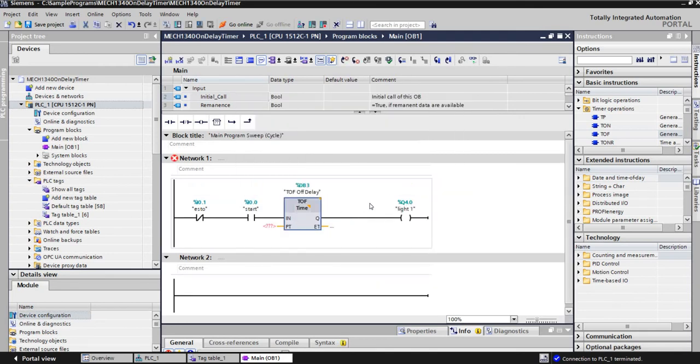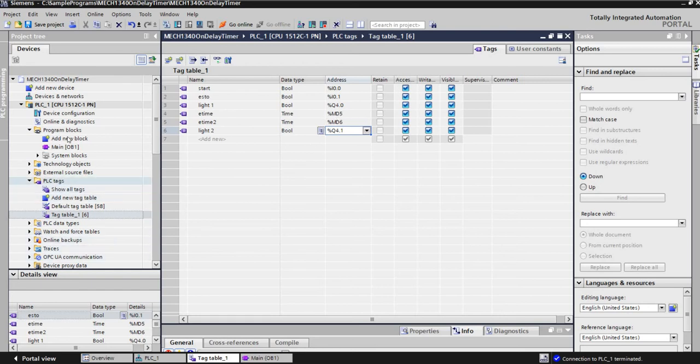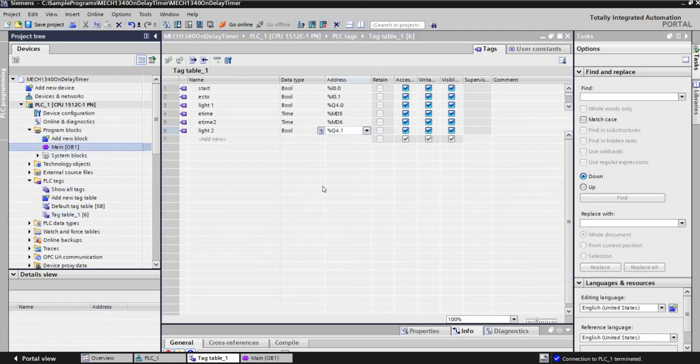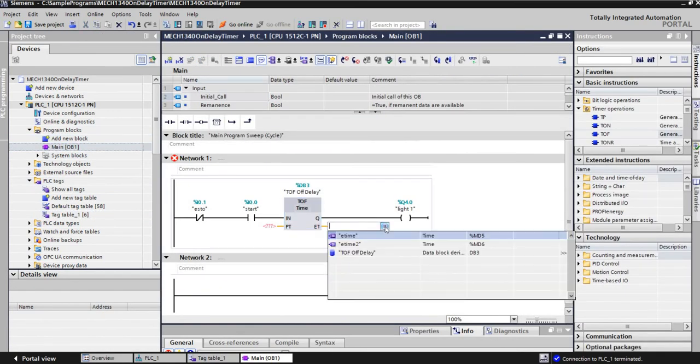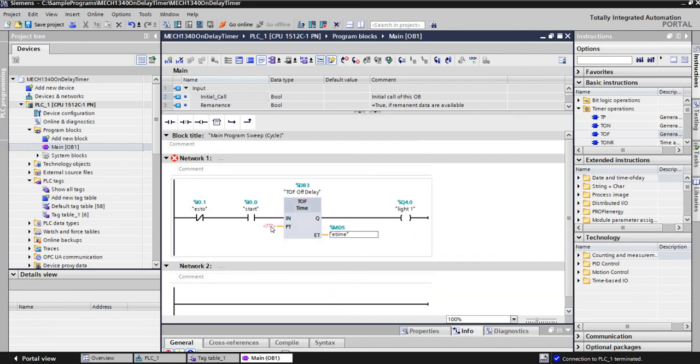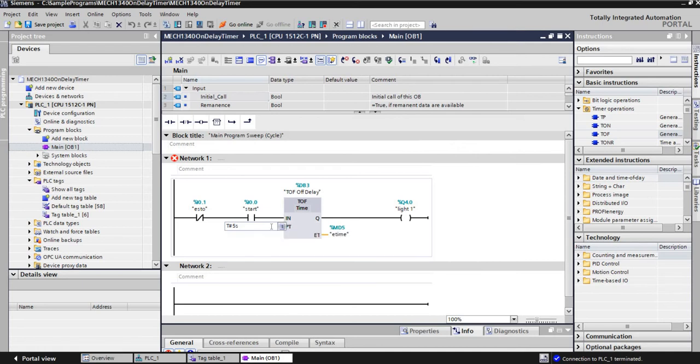So this timer is going to set up the same way we did with the on-delay for the most part. I've already made in the tag table here, so if I bring up the tag table real quick, I've already made the elapsed time right here, MD5, which I'm going to pull in. So if I go back to the main block over here, right here, elapsed time MD5, so I'm going to put that in. And then right here, I want to make sure that it is a T pound sign. And let's just do five seconds so it's quick. So now we have our off-delay timer.